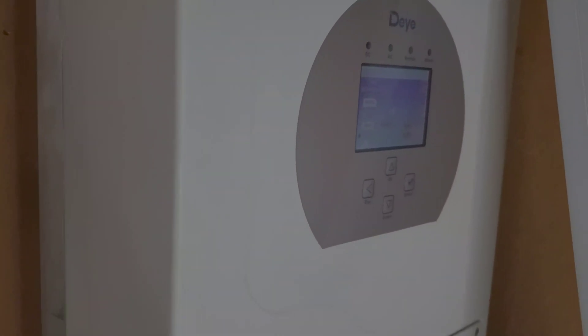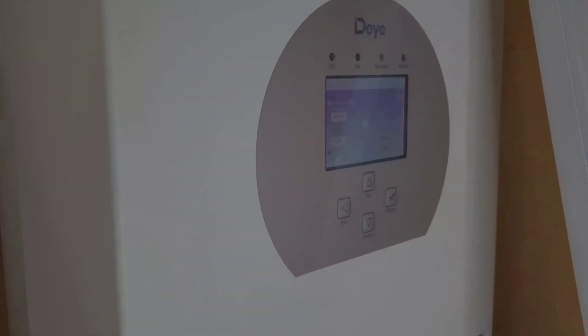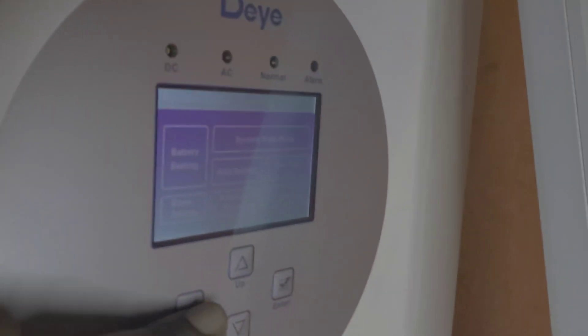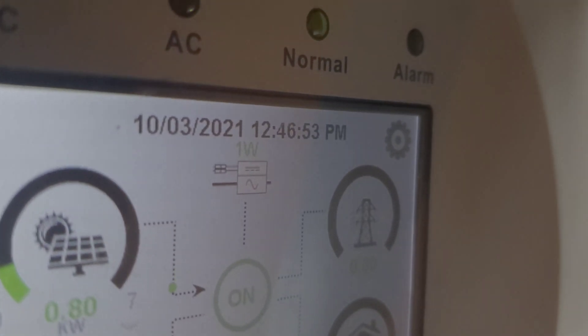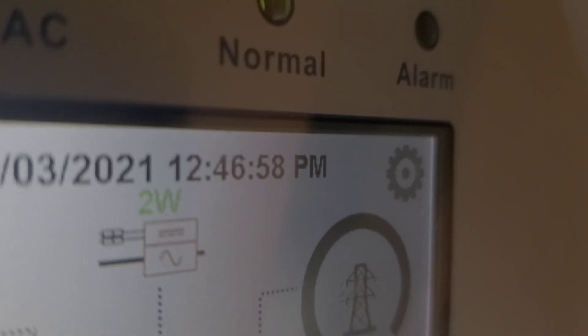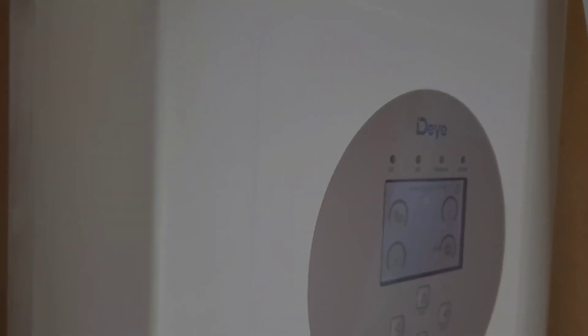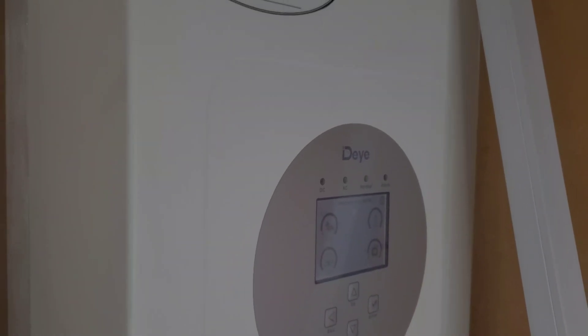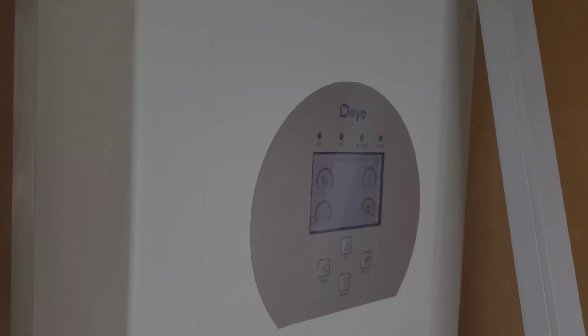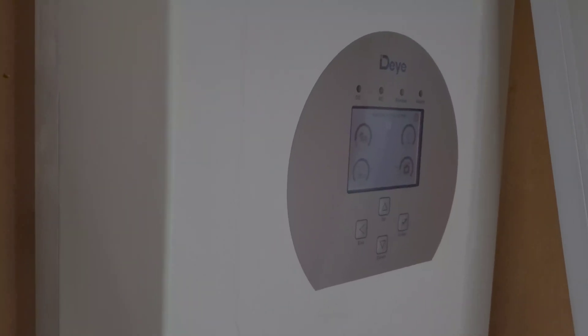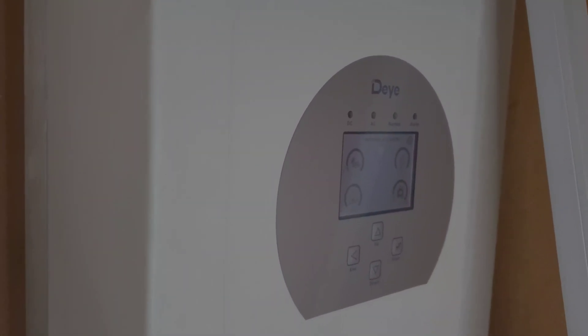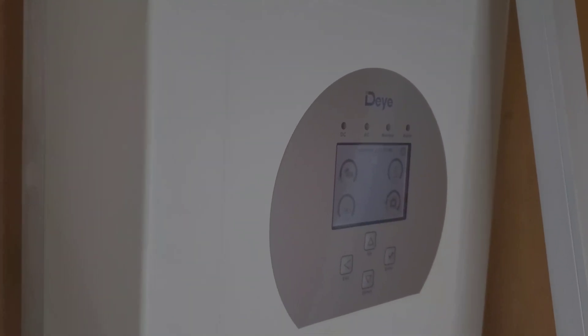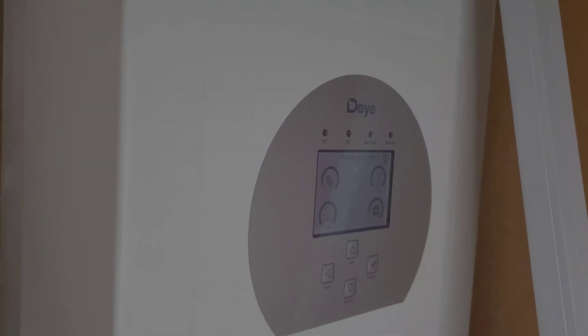So how does it manage it? First of all in the mornings, once it's morning time it sends a signal. So it sends actual voltage, it says the grid is available. So my battery inverter forms the grid. Without the battery inverter forming the grid, that inverter cannot function. In Nigeria we don't have a smart grid and we don't have the ability to sell back to the grid, so I have to form the grid. And the way I form the grid is using this inverter, the battery inverter forms the grid.